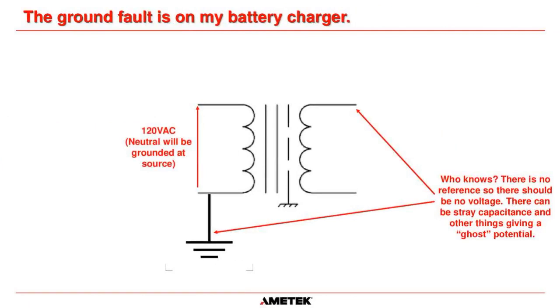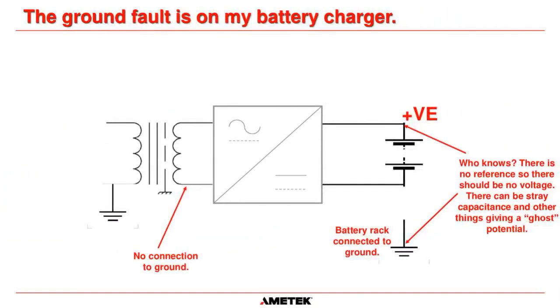So if you got a multimeter, let's say this is a 120 volt secondary, and you went on this terminal here to ground, what would you measure? And the answer is, who knows? Because there's no reference. So there should be, in theory, no voltage. There can be stray capacitance and other things giving a ghost potential, and your meter will add some impedance to that as well. So you might see it start at 0 and then start going up or something like that. But in truth, that's due to external references. There is no potential between this point and ground. And obviously that's exactly the same for the neutral to ground. There's just no reference. Okay.